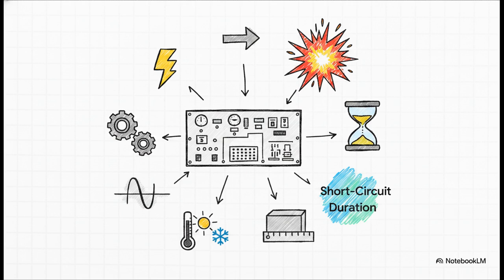Choosing the right switchboard, whether you're running at 3.3, 6.6, or 11 kilovolts, means locking down your supply voltage, continuous current, short-circuit duration, switching frequency, supply frequency, ambient conditions, and the physical footprint. But when a violent fault occurs, 2 of these suddenly matter way more than anything else: your maximum short-circuit current, which defines the sheer thermal and mechanical stress, and the short-circuit duration.